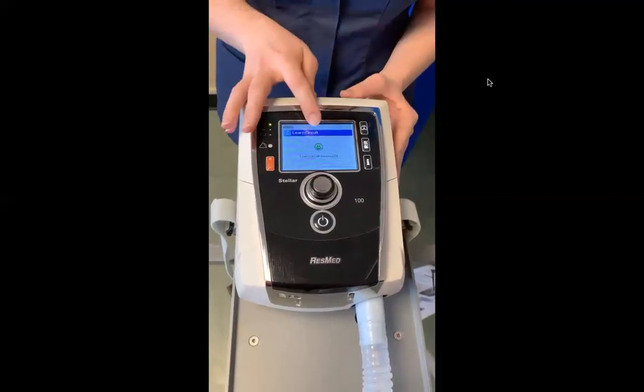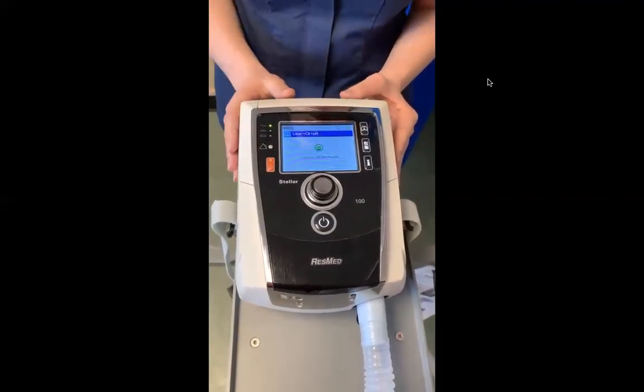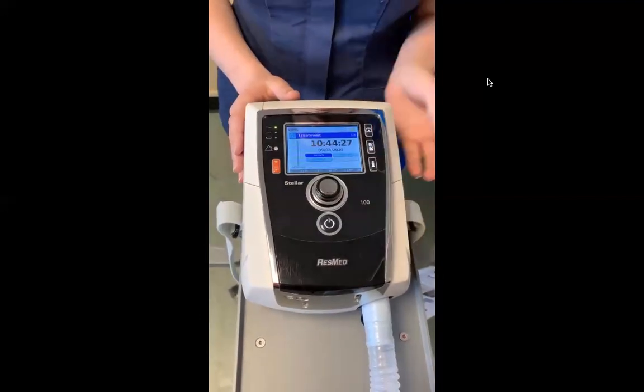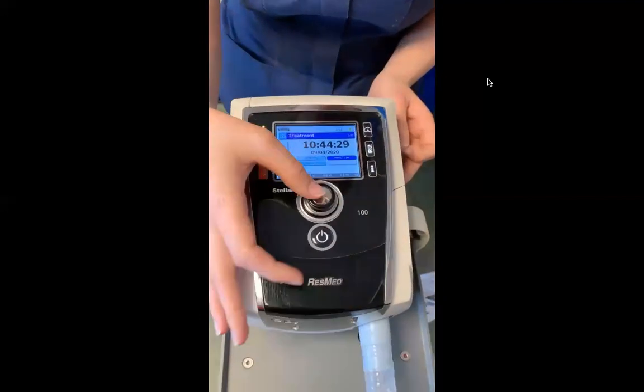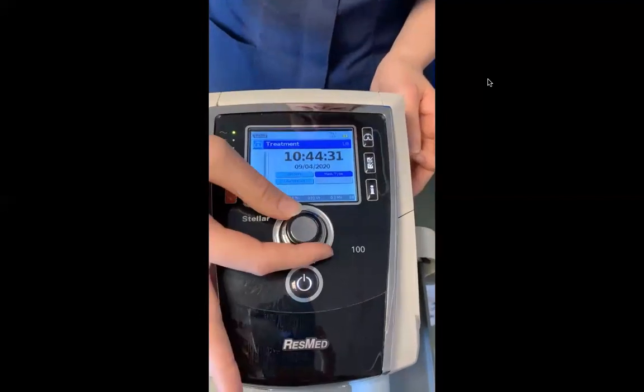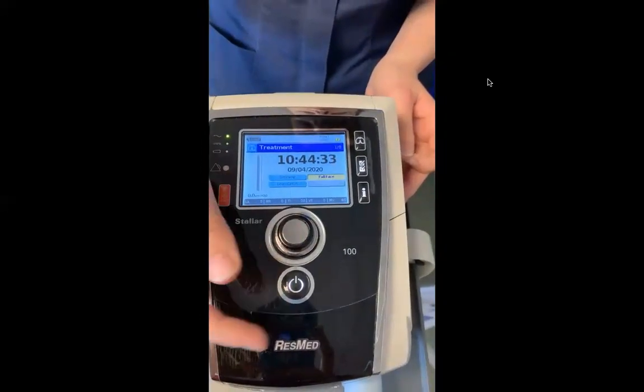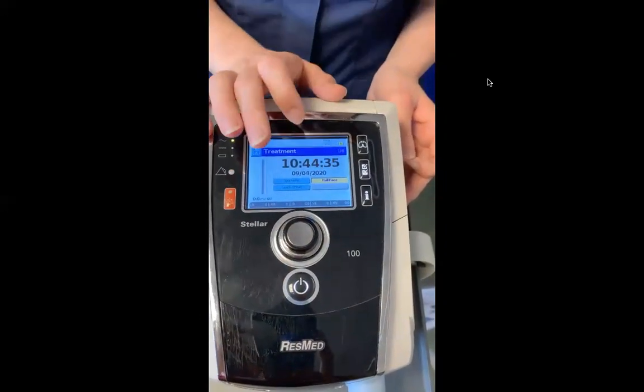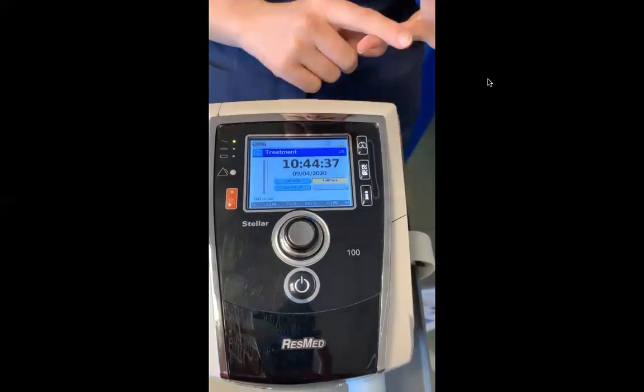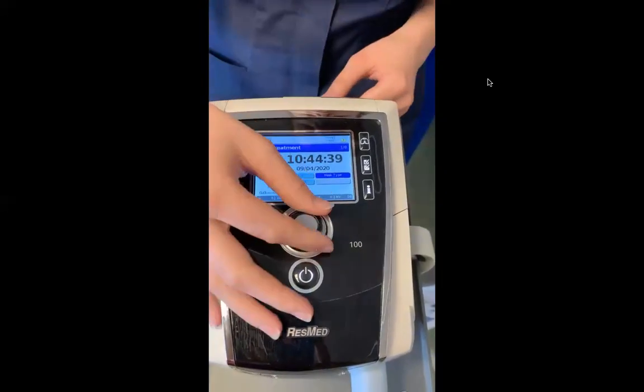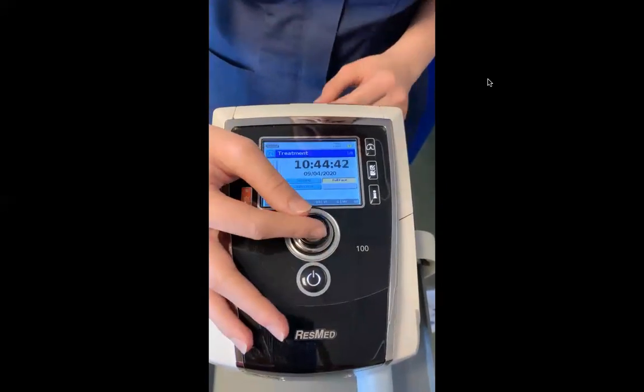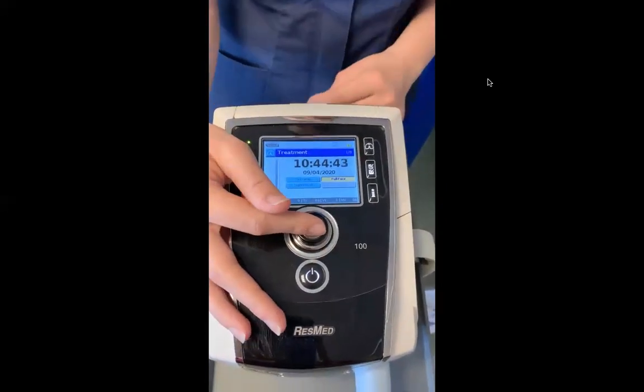Okay, so it's come up with a happy face, so it means that it's safe to use and we can now use the ventilator tubing. The first thing you can do is check your mask type. You move this spinny thing here, you click on it and it says full face. We should only be using full face. There are settings for paediatric and trachea. However, in an adult setting, we should only be using the full face mask unless a consultant has said otherwise.